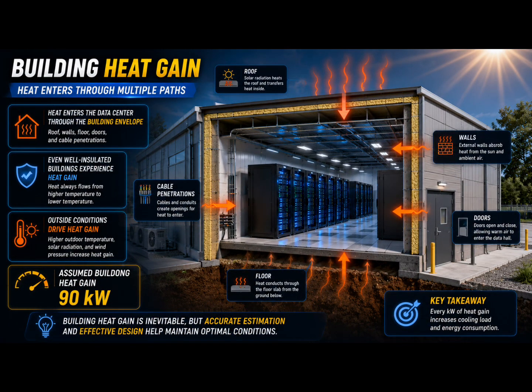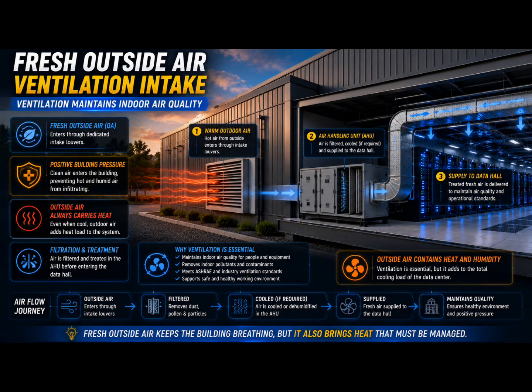Next, the building itself. Even with excellent insulation, heat continuously enters through the roof, the walls, the floor, the doors, and cable penetrations. This is known as the building heat gain. For our project, we'll assume 90 kilowatts. Finally, there is fresh outside air. Data centers require controlled ventilation to maintain indoor air quality and positive building pressure. But outside air always carries heat. Before it enters the room, that heat must also be removed. For our design, the ventilation load contributes 180 kilowatts.